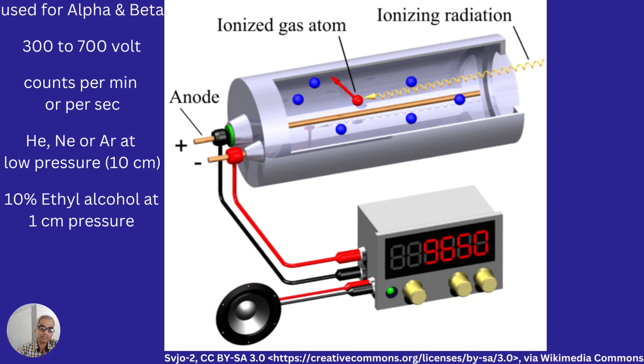When an atom gets ionized, the electron may strike other atoms and create an avalanche of electrons, which could cause a discharge between the cathode and anode. To avoid this discharge, 10% ethyl alcohol at 1 centimeter pressure is used as a quenching agent mixed with the gas.